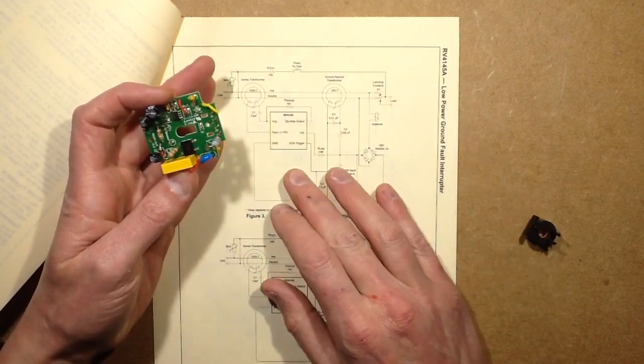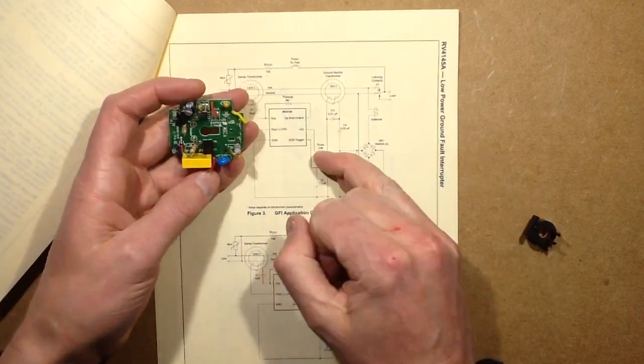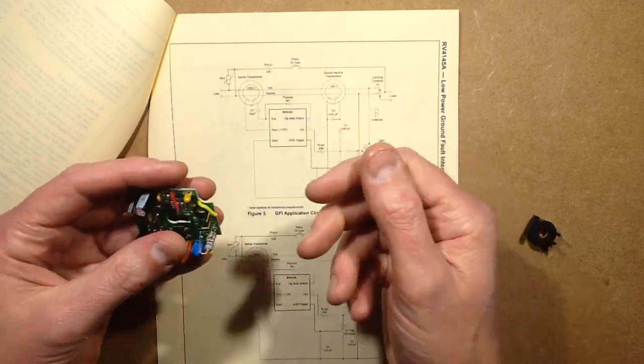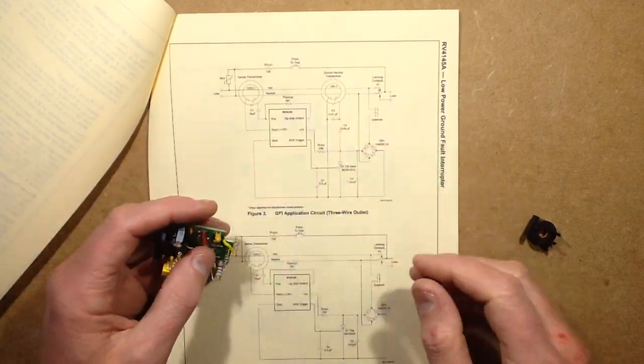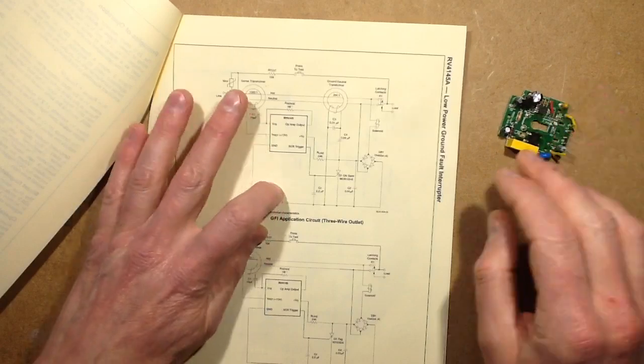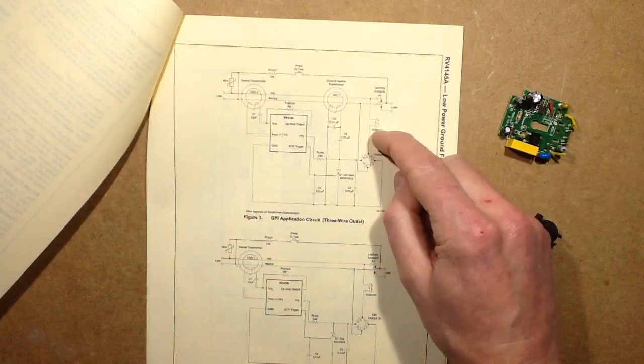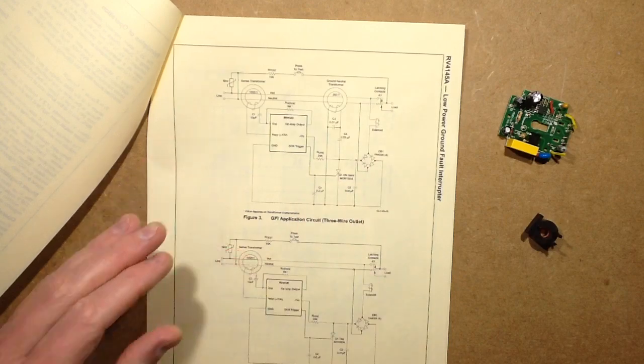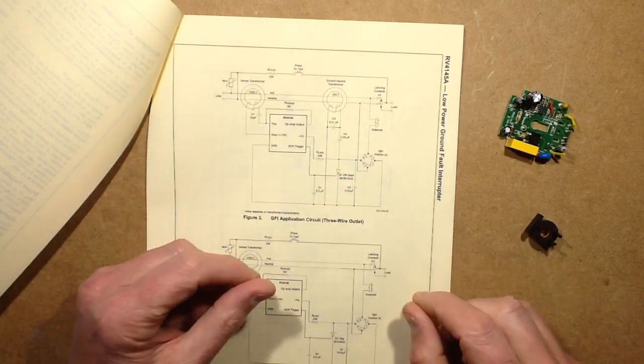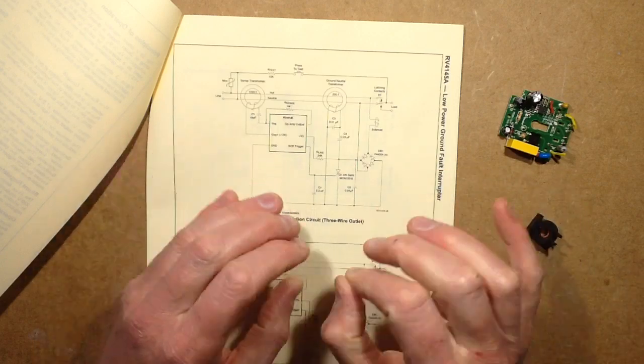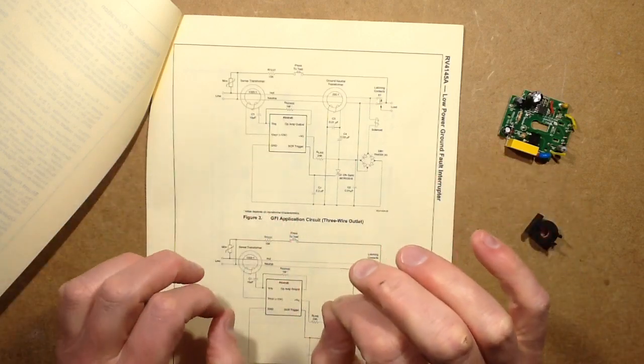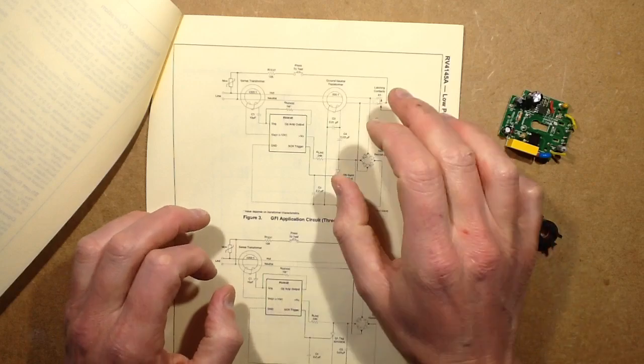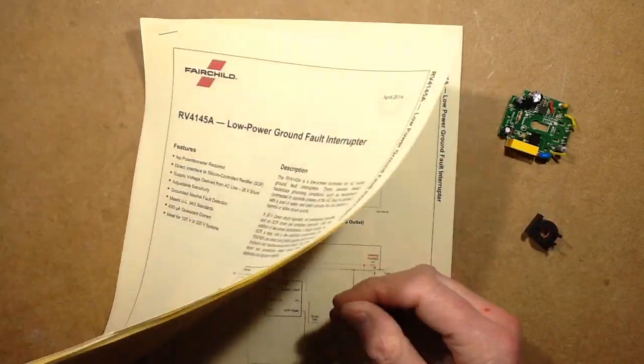What's interesting is that this chip is optimized for low current operation. It's got a 24k resistor and it's got a zener inside and it's just really designed for low current operation. And to trip the coil out, it just drives the coil directly from the mains by bridging out its bridge rectifier with a thyristor. And that means that the little solenoid that punches off, that switches the breaker off, is only going to be operational for as long as it takes to do that or it would just burn out.